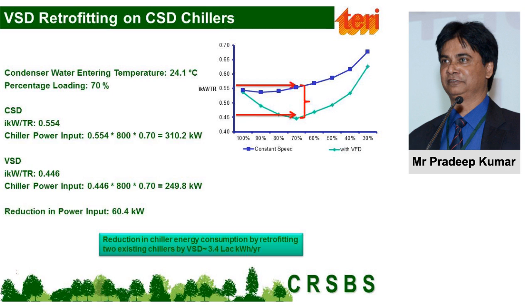So when we worked on it, we took the hourly data from the chiller logbook and worked it out for each hour and calculated the total saving. And we found that, okay, if we can make two chillers work as variable speed chillers, then the saving is going to be somewhere around 3.4 lakhs, depending upon the percentage loading and the ambient wet bulb and other things.